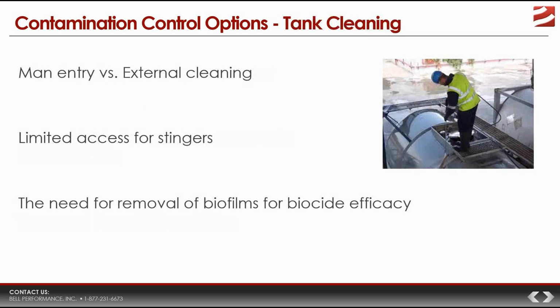So that means tank cleaning. Now, man-entry tank cleaning is going to be the gold standard for this, but not many companies have the ability or the desire to really do this. So we do the best we can with external tank cleaning. That's what companies, fuel polishers and fuel treatment service companies rather, will do. They will not do man entry into the tank. They will use stingers and suction and hoses to try and suction and remove as much of the biofilm and, of course, as much of the water out of the tank as possible.